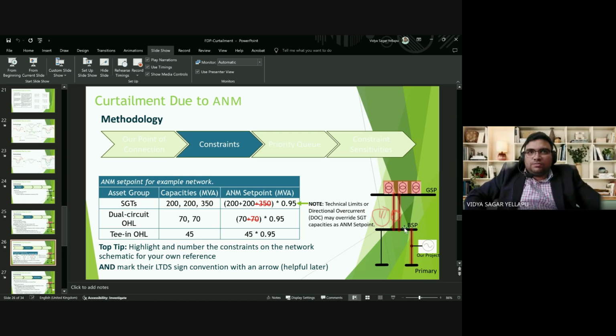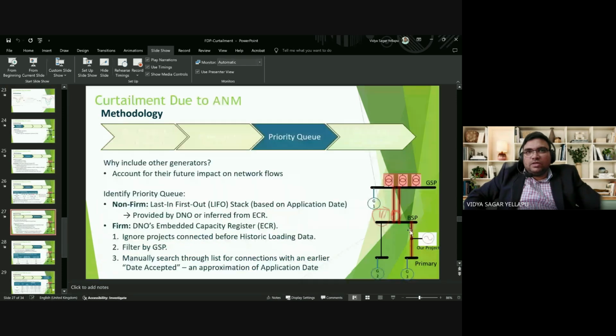Coming to this tee-in overhead line, the T means it is like a T, that is, not looped in, looped out. Looped in, looped out connections are generally given for demand connections, which require security of supply. If one section goes offline, the supply can be restored through the other way. But that is not required for generators, because security of supply is not that much of a concern for generators. We consider a tee connection to reduce the cost of the cable going to the project. That is the concept behind this tee. So since this project is teed in, the derating factor is directly applied, and as there is no other line, all these things are to be taken into consideration in the assessment of curtailment for this project.